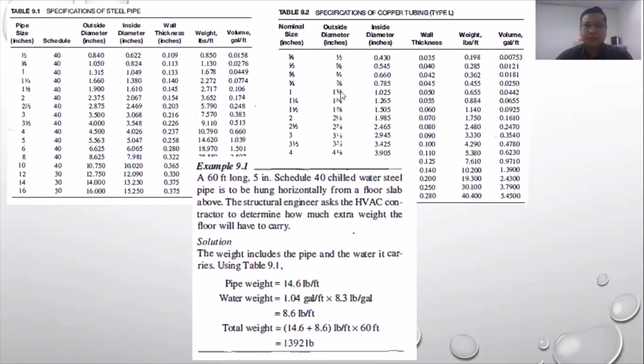Okay, in table 9.2, we don't have a schedule, but the properties are informed by the L type. It means the medium thickness. So 3/8 inch, and outside diameter is ½ inch, and so on. So it informs all specifications of pipe, both steel and copper.